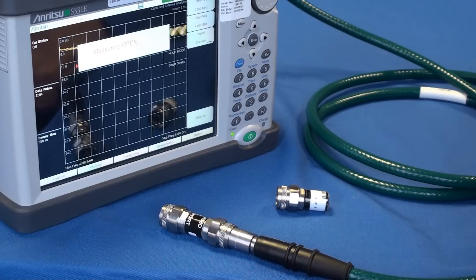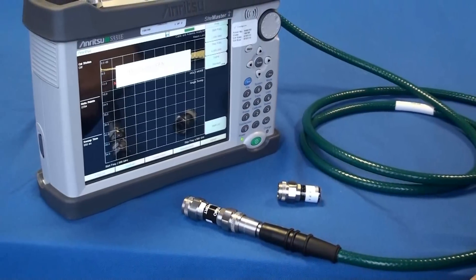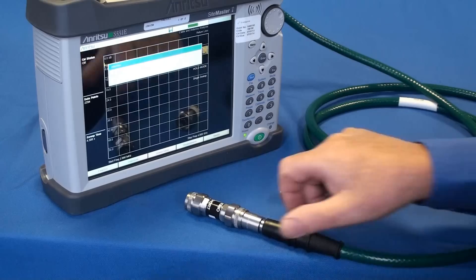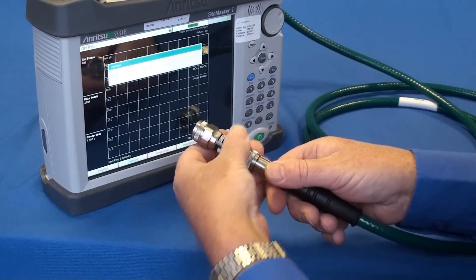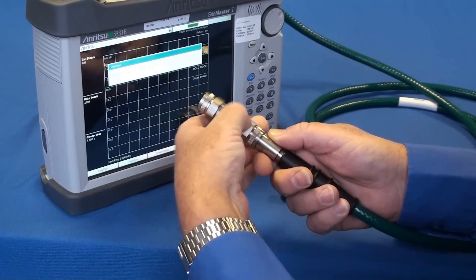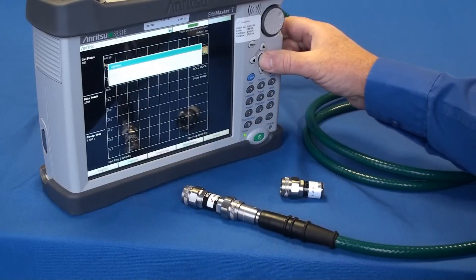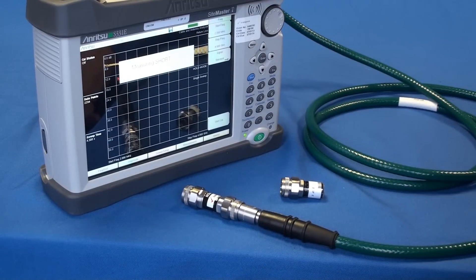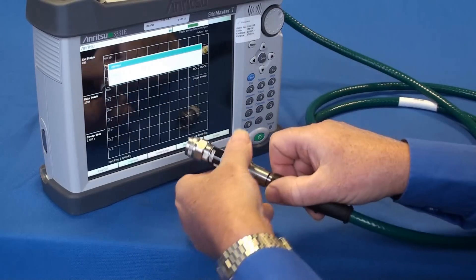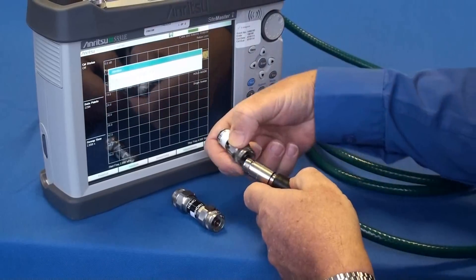When finished the instrument instructs you to connect the short. Again carefully do so and as instructed press enter on the Site Master. Following this, when instructed to do so, connect the load to the cable and select enter on the Site Master.